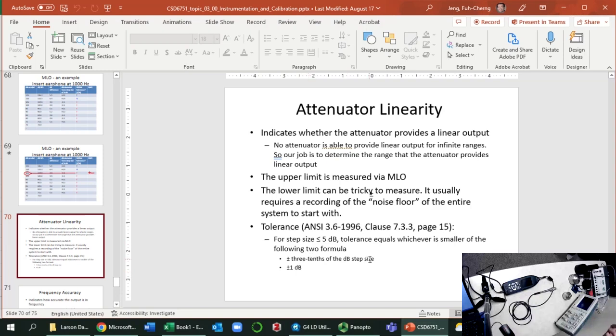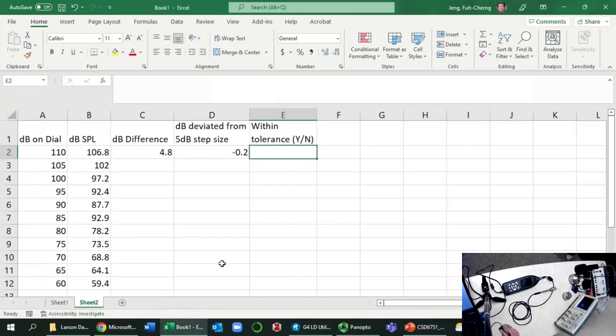So 3/10 is 0.3. 5 dB multiplied by 0.3 is 1.5. Are you with me? So the first number is 1.5. The second number is 1. We use the smaller number so that our calibration is more strict. Whichever is smaller, we use that as the criteria. So in this case, 1 dB is smaller, so we use 1 dB as the tolerance. So tolerance is 1 dB. Let's go back to here. Is it within 1 dB tolerance? Yeah, right? So yes. So far so good?